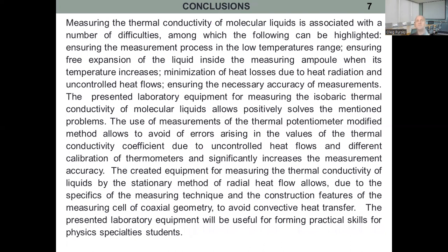Conclusion. Measuring the thermal conductivity of molecular liquids is associated with a number of difficulties, among which the following can be highlighted: ensuring the measurement process in the low temperature range, ensuring free expansion of the liquid inside the measuring ampoule when the temperature increases, minimization of heat losses due to thermal radiation and uncontrolled heat flows, and ensuring the necessary accuracy of measurements. The present laboratory equipment for measuring isobaric thermal conductivity of molecular liquids allows positively solving the mentioned problems.